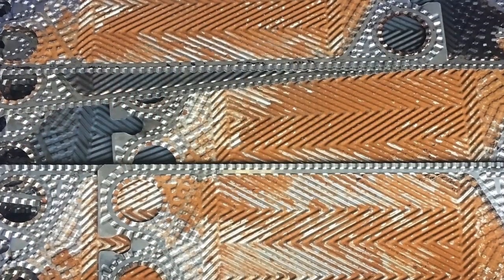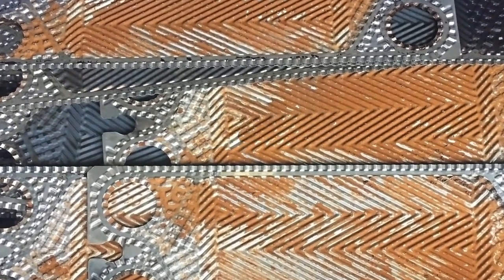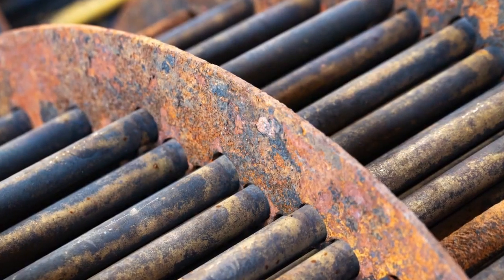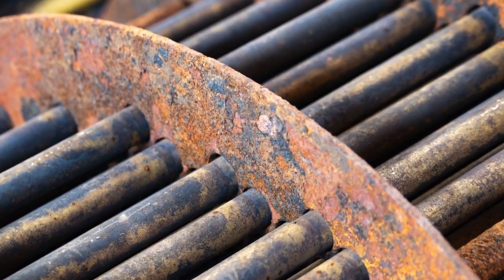As we have seen in other videos, when designing a heat exchanger, it is necessary to take into consideration the fouling factor or an oversizing in terms of exchange surface to account for the possible fouling of a heat exchanger. Clearly, it depends a lot on the fluids that pass inside. When we have exchangers that treat clean fluids, the problem of fouling obviously does not arise. So we can size the exchanger very precisely based on the working conditions without taking too much into account what could be fouling and therefore a reduction in the exchange surface.